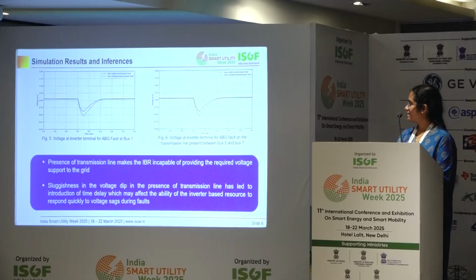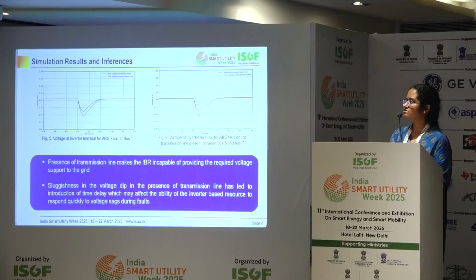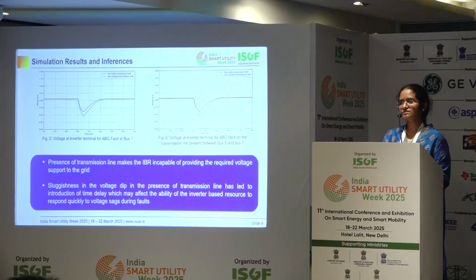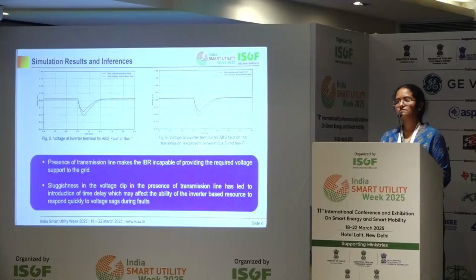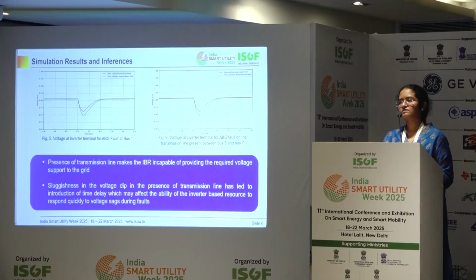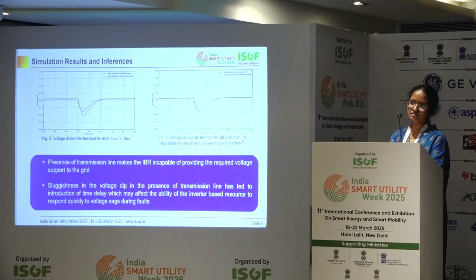These are the inferences we get from these results. Point number 1, it cannot provide the required reactive power into the system. It also creates a time delay in the system, and the voltage sag might be there in the system for a longer duration. The protection settings which have been made for normal conditions might not be satisfied for the voltage dip which is there, and the fault might persist for a longer period of time instead of islanding the IBR, if it is not a short term fault.